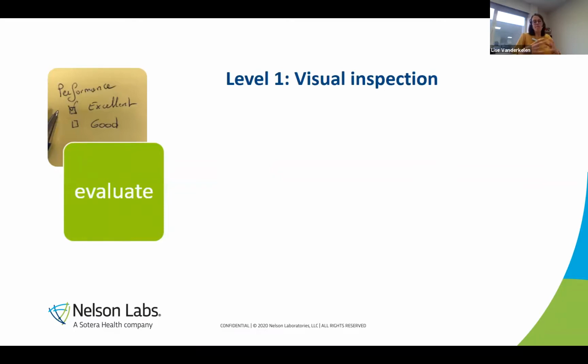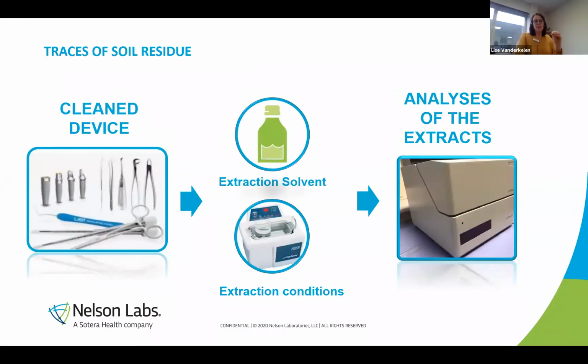So level 1, visual inspection, very important parameter. Then we're going to look for traces of soil residue. We're going to take our clean device and try to remove any residue of soil which is visually not clear because it passed level 1, and see whether or not there are traces of soil still present. So we will extract the soil from the device under certain extraction conditions and analyze that.